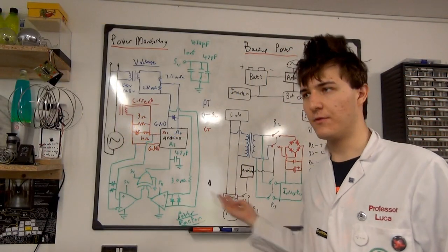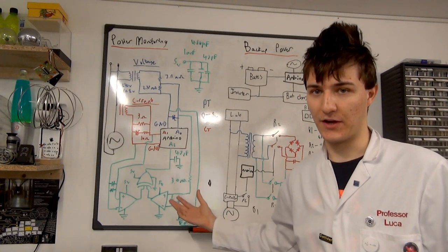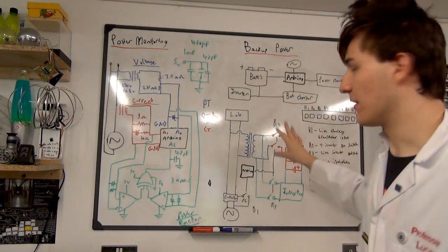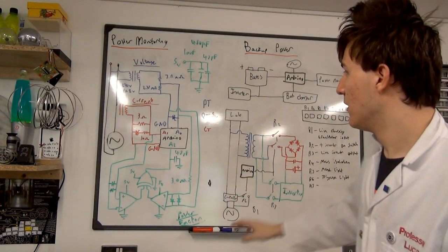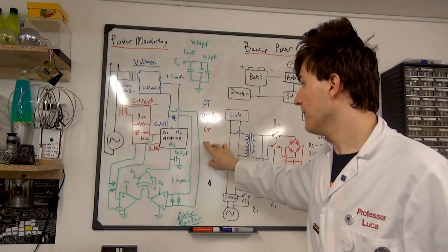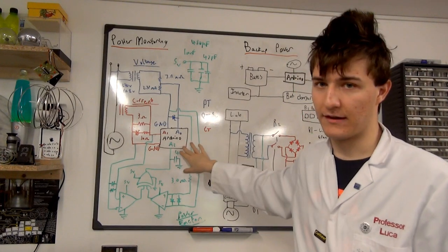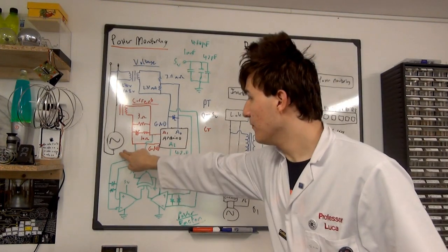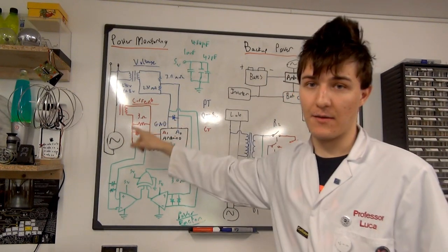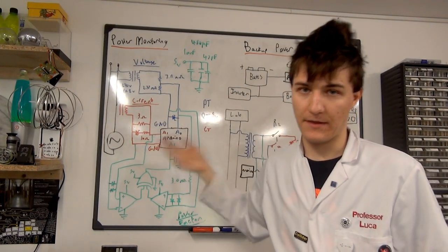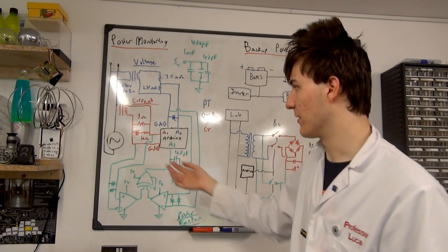Okay so we've come over to the second whiteboard here because I already had the circuit diagram drawn up when I was actually designing and implementing the project. Now you can ignore everything on this side because that's for the backup power. Like I said that'll be the next video released in a week or two. So there's three main systems here and I've put them in three different colours to make that clear. The Arduino sits in the centre and that does all the data processing. Over here we have the mains power coming straight in from the armoured cable that you saw and that lights up the lights on the front panel that says panel live. That just shows that there's power entering the cabinet and that the cabinet is live so you obviously don't want to touch anything unless you turn the power off.